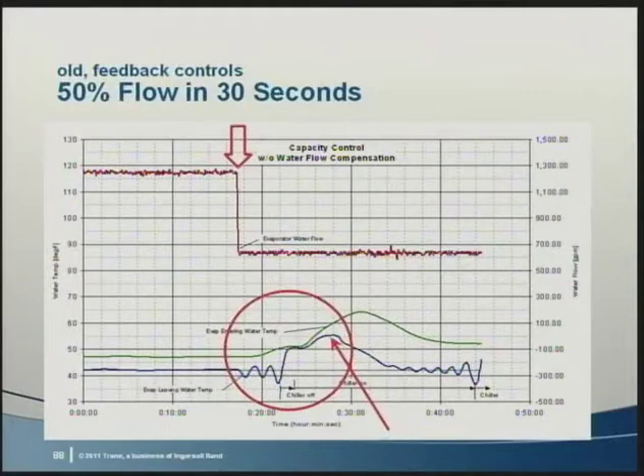Too coarse means overcompensating and spinning out of control, as you see in the graph. For this reason, you might have set the delta T at half flow condition. What this would do is make the adjustment too fine at full flow, making the chiller react to change much slower. The chiller would stay online, but would not react as fast.